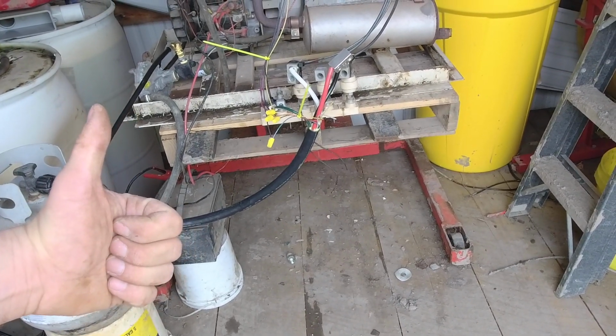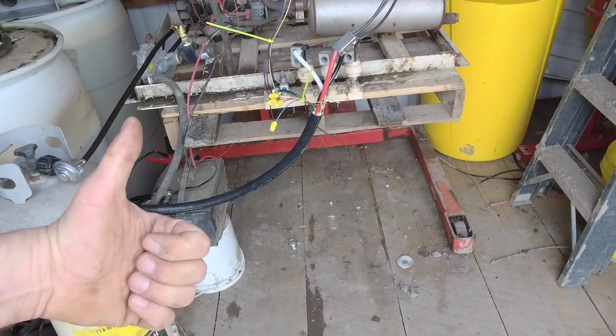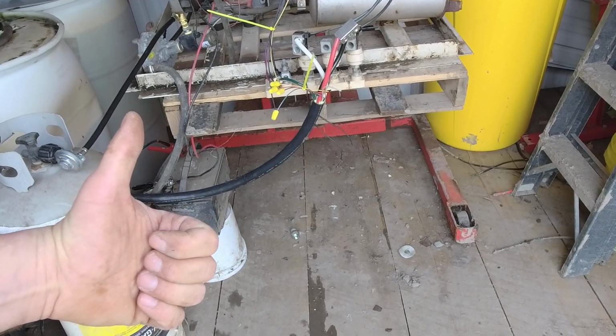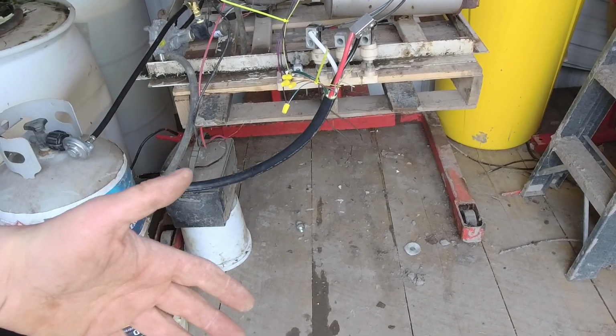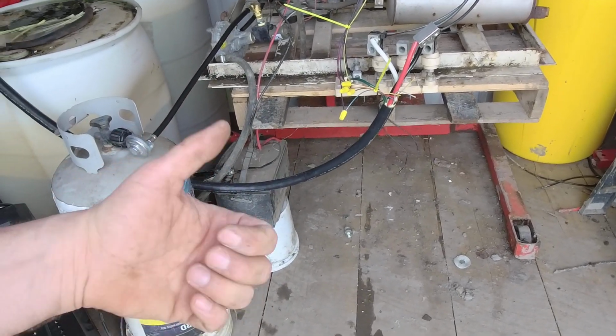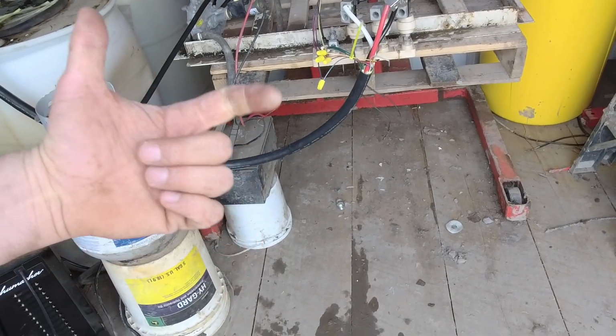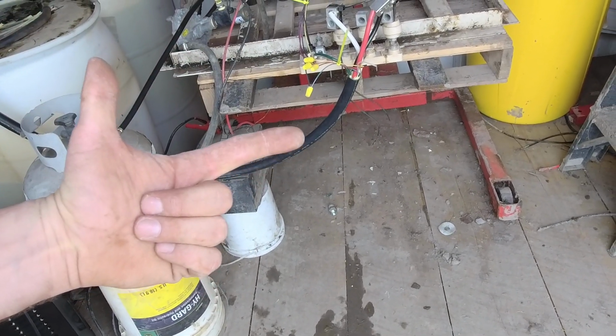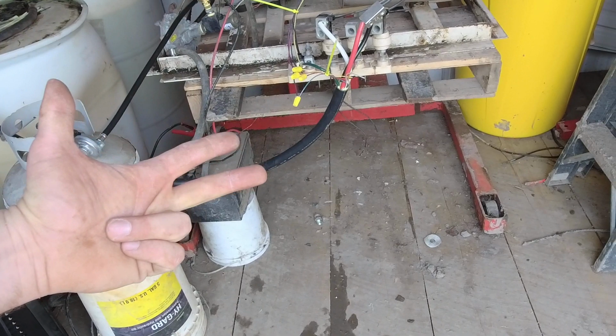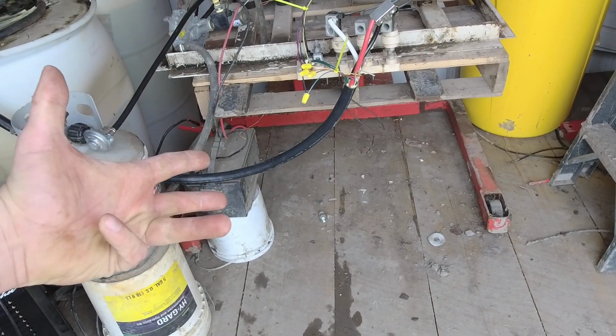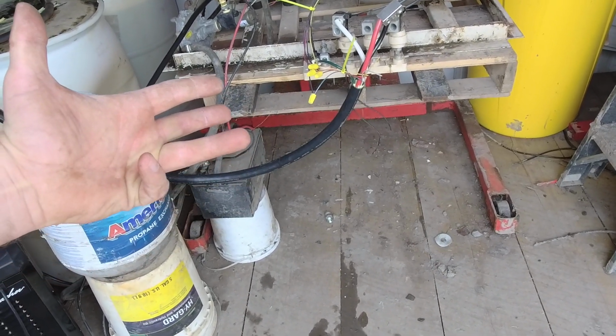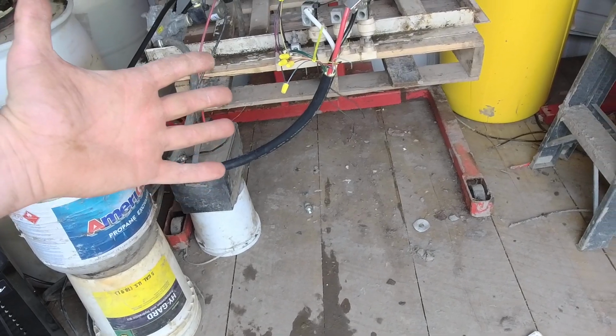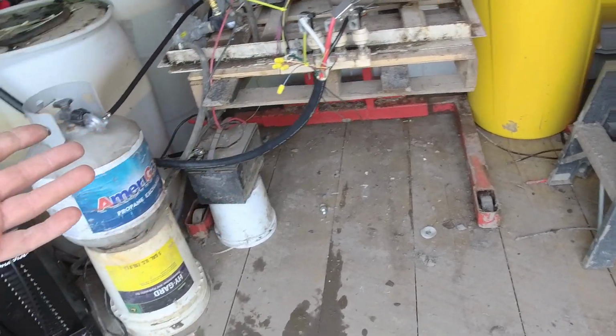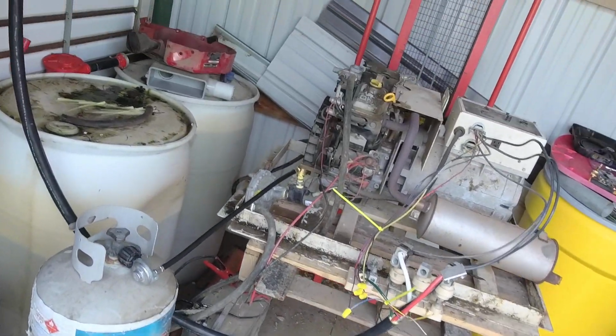14 gauge or 12 gauge is good for 20 amps. Let's start at the top of your typical household stuff: 10 gauge is good for 30 amps, 12 gauge is good for 20 amps, 14 gauge is good for 15, 16 is good for probably 10, and 18 is probably even less than that, like 7.5 or 8.